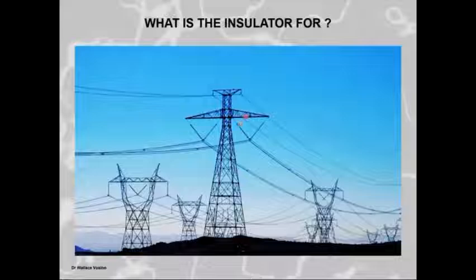We've got the birds excreting onto the insulators, which can cause pollution problems. We then have airborne pollution particles coming around and polluting these insulators, and basically changing the resistance of the layer on the insulator to such an extent that when you get enough wetting, an electrolyte forms and the insulator flashes over. Oh my goodness. An insulator is not just an insulator. An insulator is quite a critical element, because if that insulator had to fail mechanically, this line drops. If the insulator fails electrically, you can't transfer the energy, because you've got something taking the energy down to ground at the tower structure. So this insulator is a very critical component of this whole line and the line's functions.